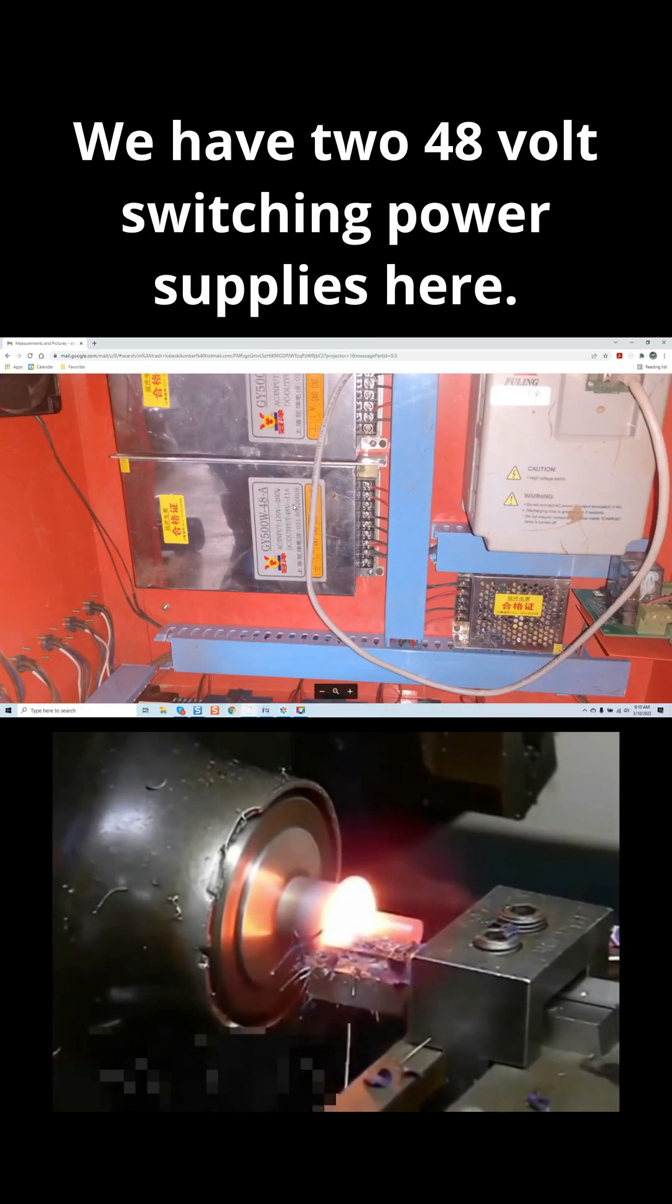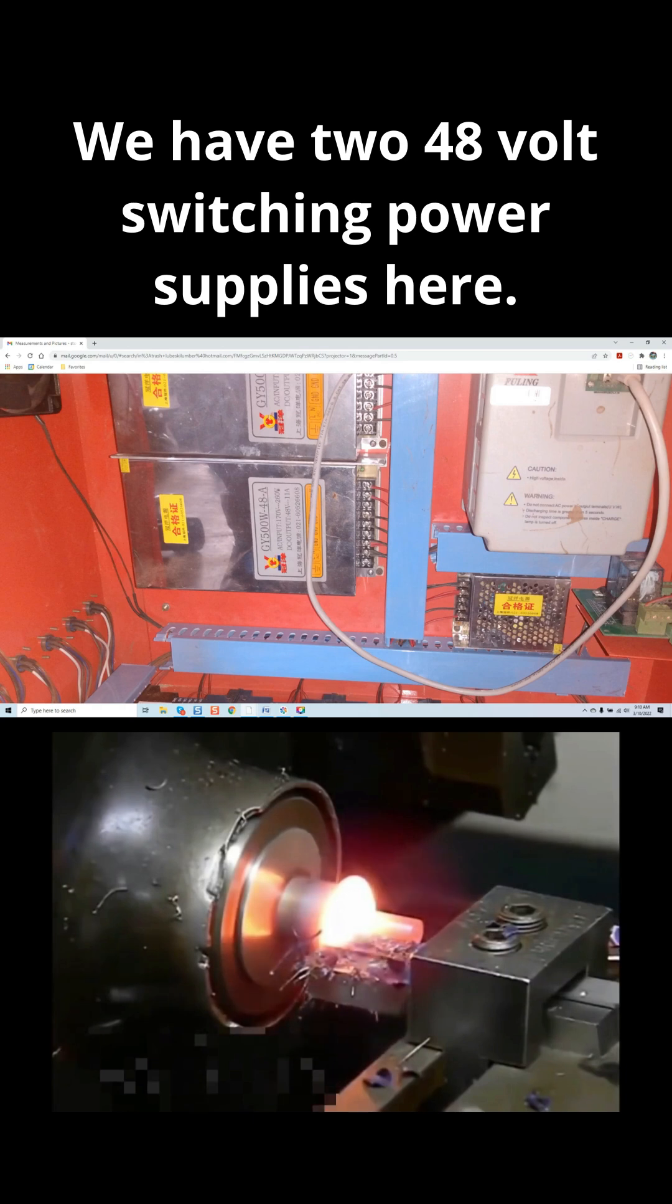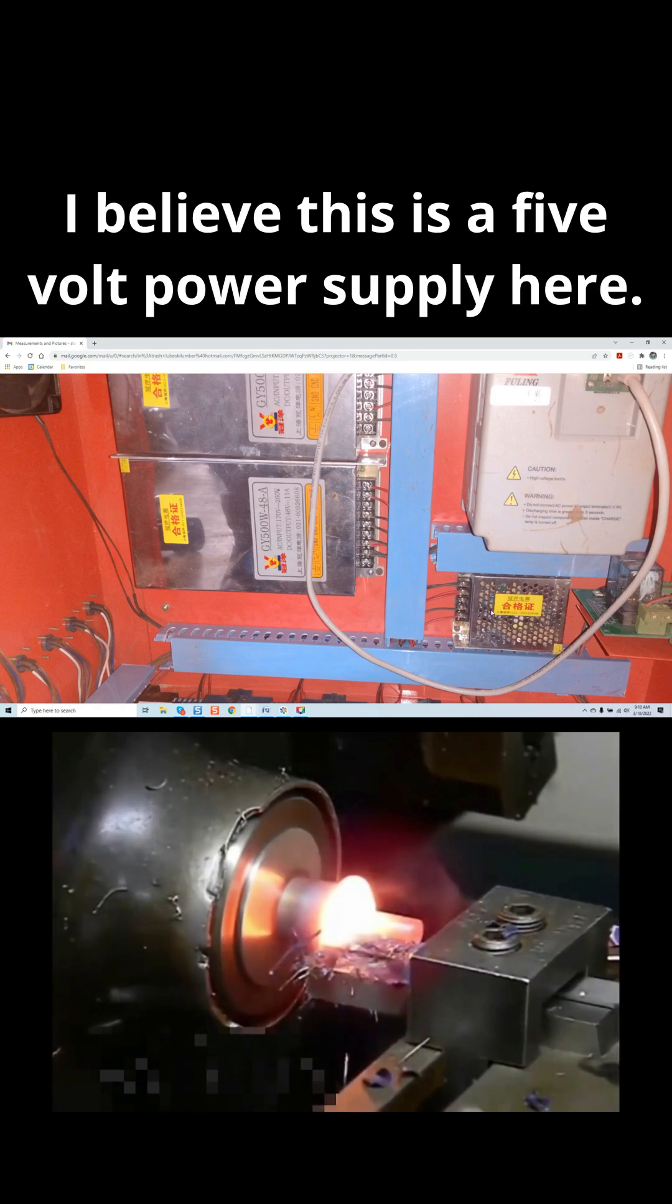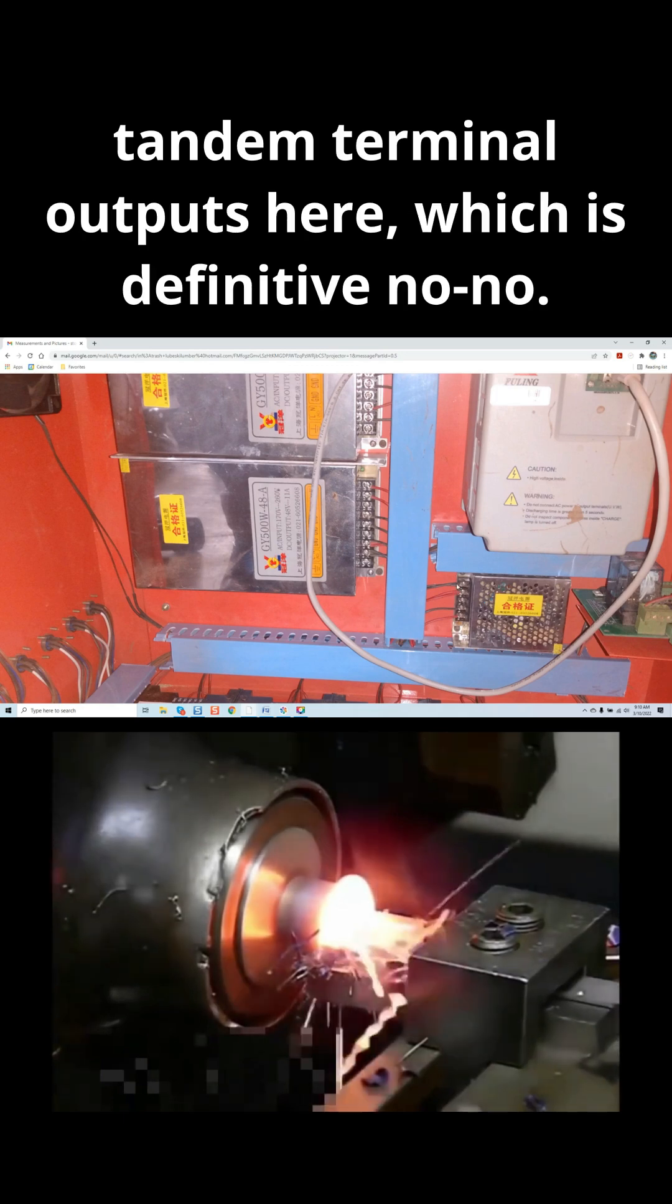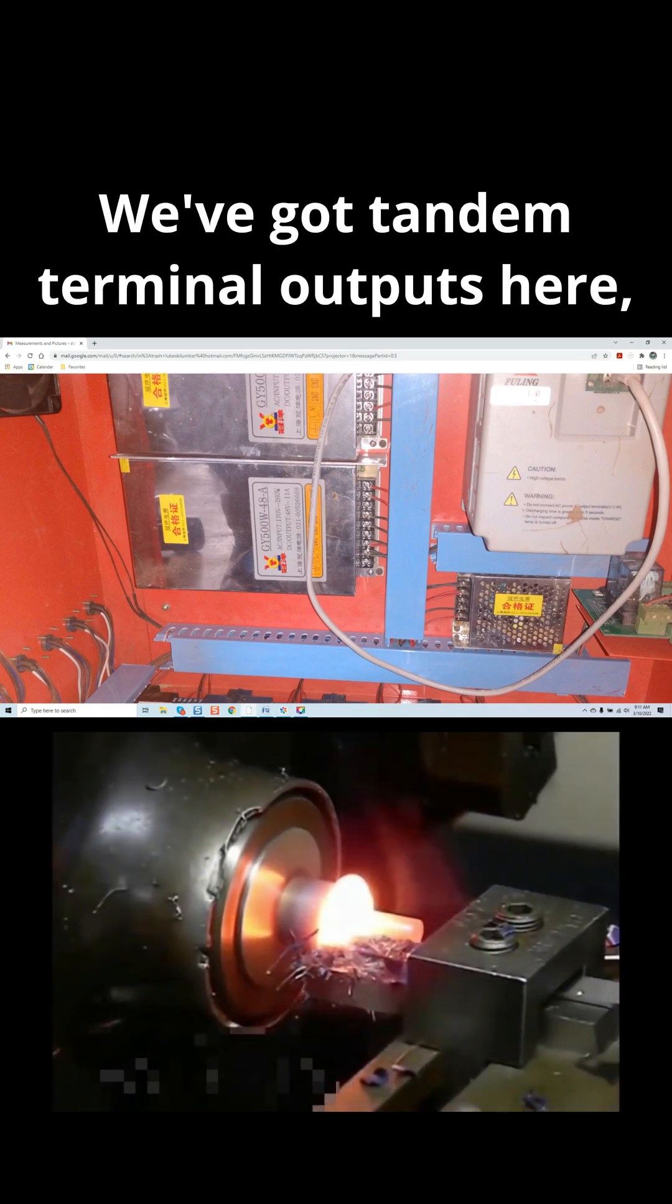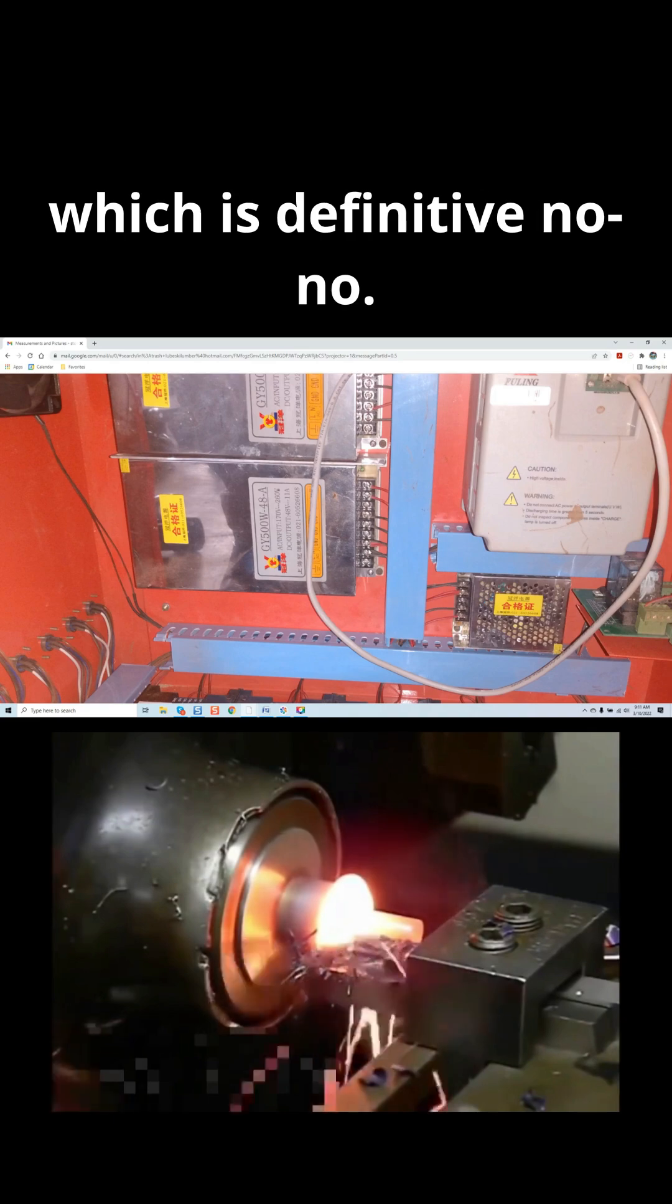We have two 48-volt switching power supplies here. I believe this is a 5-volt power supply here. We can see that we're using tandem terminal outputs here, which is a definitive no-no. We've got tandem terminal outputs here, which is a definitive no-no.